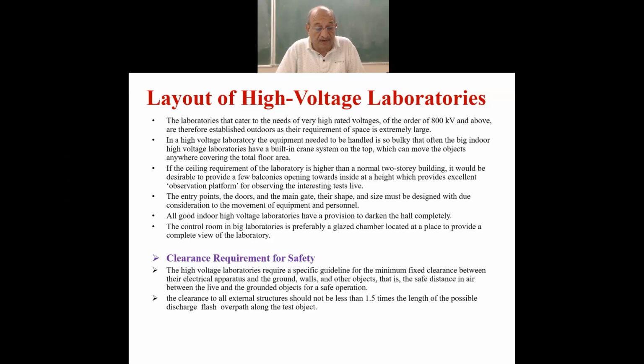The laboratories that cater to the needs of very high rated voltages of the order of 800 kV and above, as we talked, are established outdoors, sorry, I said indoors, are established outdoors because of the large requirement of space. And in a high voltage laboratory, the equipment to be handled is so bulky that often the big indoor high voltage laboratories have a built-in crane.